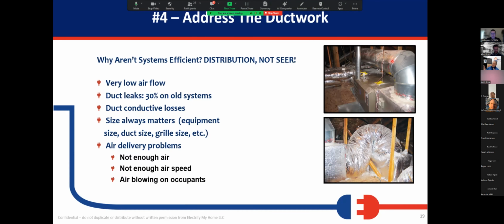We've found that if we go to a 3-ton system and check static pressure and it's running at 1 inch of static with a 1200 CFM blower assembly, and we check the fan tables, we can see that at 1 inch of static it might actually be doing 750 CFM. I would be way more likely to just pop a 2-ton system in there, because I know the ductwork is adequate for 700 to 800 CFM, and I'm much closer on capacity. And that unit's going to work much better because it'll run longer cycles, and it's not going to have those deficiencies in operating capacity that you get with high static pressure. So static pressure is a huge problem.